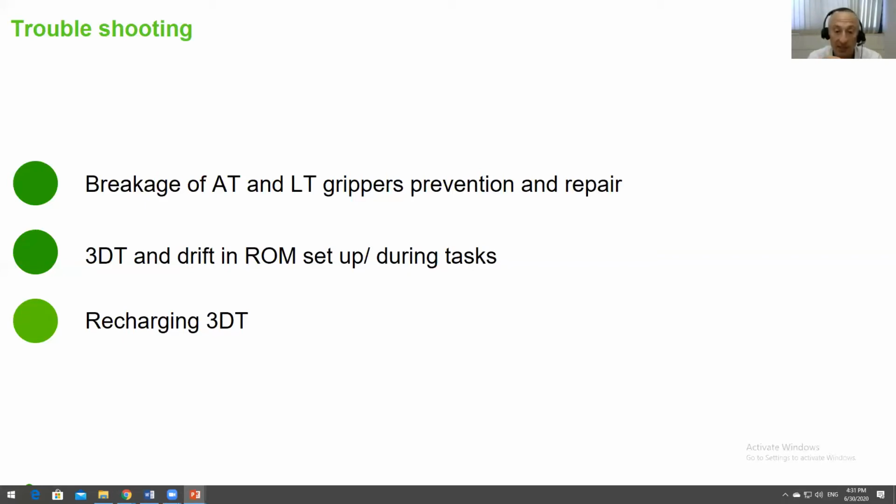So to check to see whether this is drift, you go into the range of motion setup, and you just lie the sensor flat on the table, and you click through each of the planes. And then you see if that range of motion is, after a period of time, increasing. If it's increasing, that could be what we call drift.